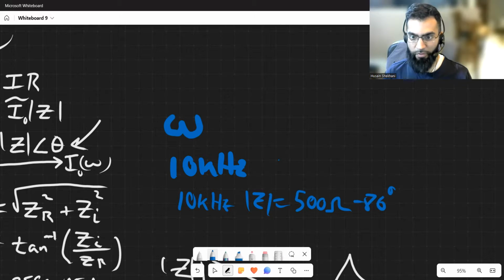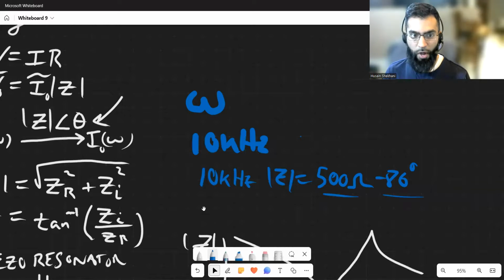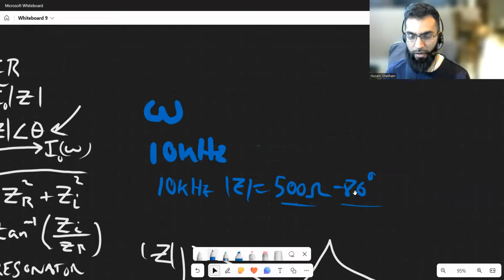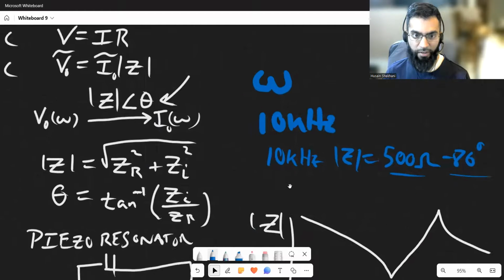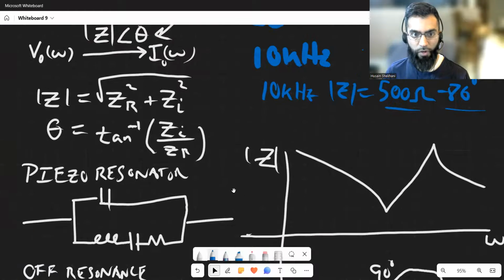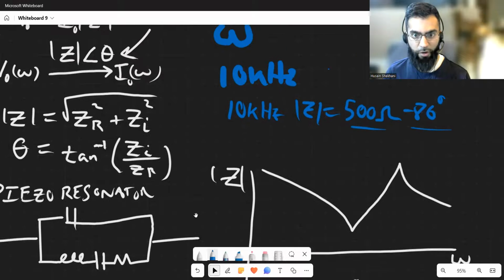That is a proper definition of impedance. It's not just ohms, or just phase angle, it's both, and that tells you that current is lagging voltage by 86 degrees at this frequency, 10 kilohertz. You divide voltage by 500 and you'll get the current amplitude. So there's phase angles, there's real and imaginary parts.